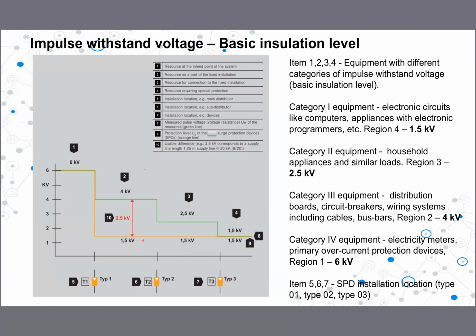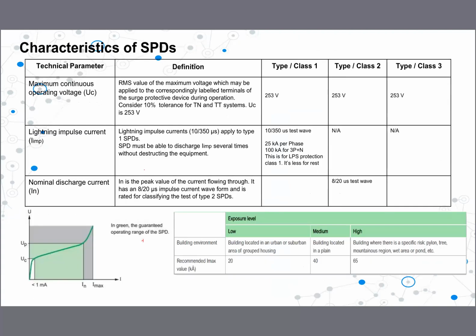Especially this one we need for type 2 SPDs, right? In type 2 SPDs, there is a nominal discharge current as well, because current discharges through this. Now here, depending on the building environment, whether it's 20 or 40 or 65, we need to decide and select the kA value suitable for this application and this site condition, because the current discharges through this. That's why the kA level is also important.